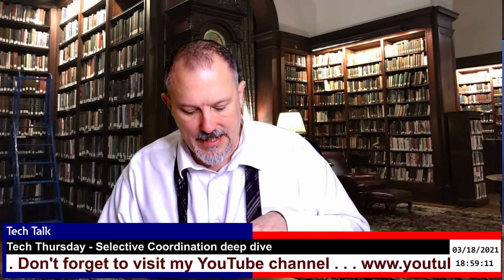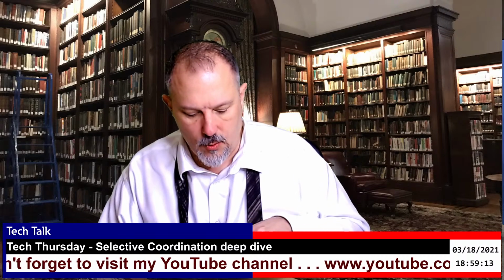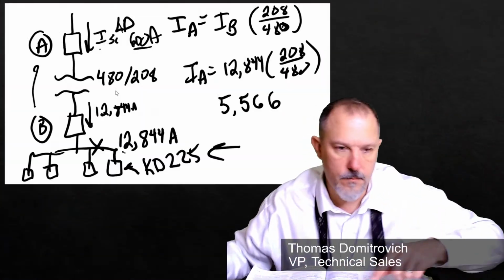Legally required standby systems, overcurrent devices shall be selectively coordinated with all supply side overcurrent protective devices. That doesn't mean you have to call the utility and hope they selectively coordinated everything in their world. Remember that Article 700 and 701 only applies to, say, 700. Okay, let's just talk about the Article 700. Okay, in a selectively coordinated system, in an emergency system, Article 700.